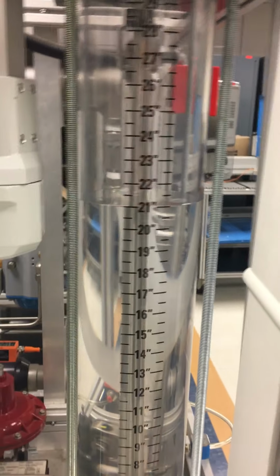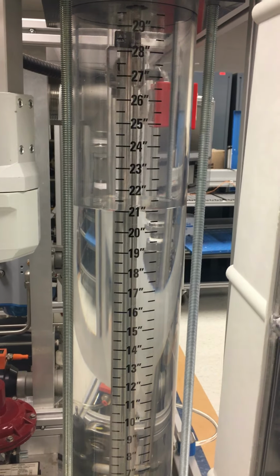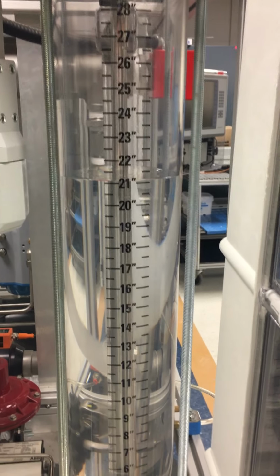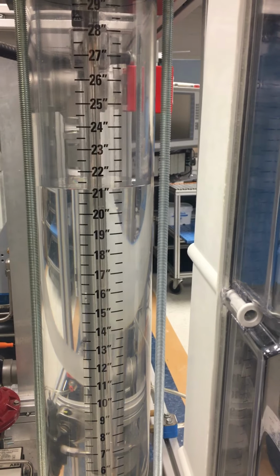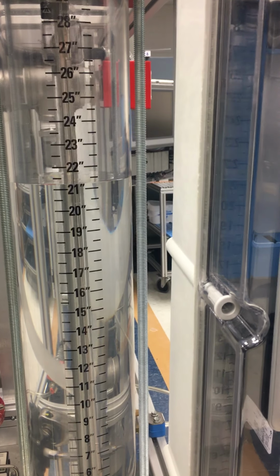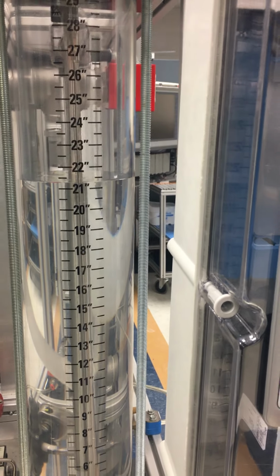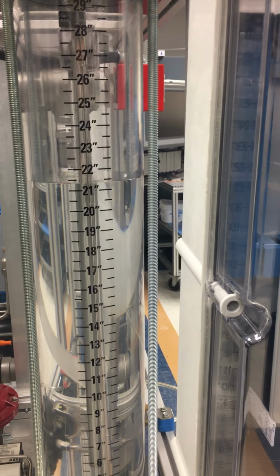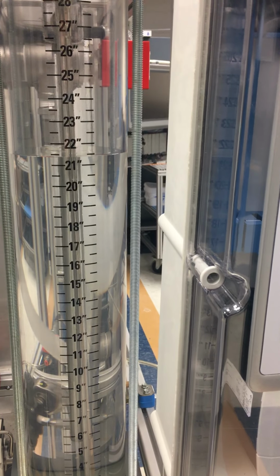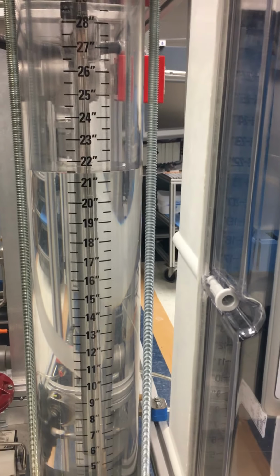So you'll realize it's really hard to maintain the water level at a certain reading very accurately by manual control. That's why we need to talk about auto control with the PLC. We will use the PID instruction to maintain the level. Later on you will see that.